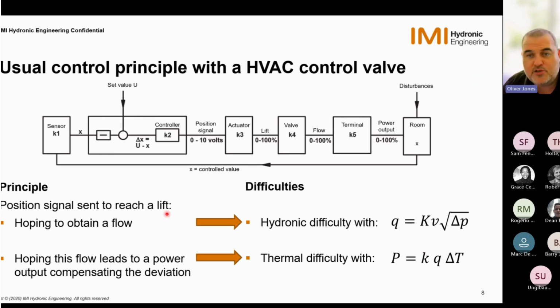So we are faced with these two difficulties. The first, our hydronic difficulty, which is expressed with a common formula, where the flow Q is equal to the kV times the square root of the dP. With the delta P variation that can happen, the flow that we're obtaining at the terminal unit is not something that is completely under our control. And the second difficulty is the thermal difficulty, where the power output depends on the flow traversing through the terminal unit and the delta T experienced by the fluid when it's going through that terminal unit. So these two difficulties are now non-linearly related to each other, making this problem a little more difficult now.